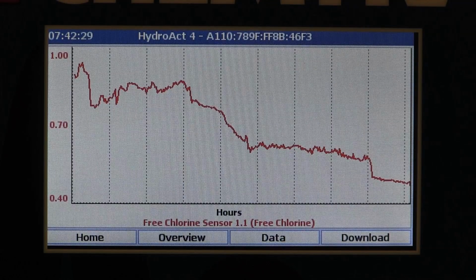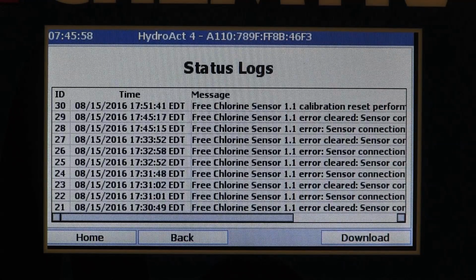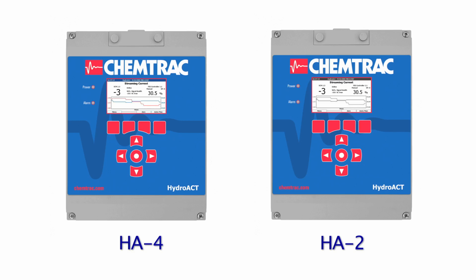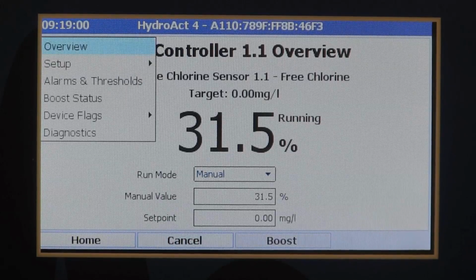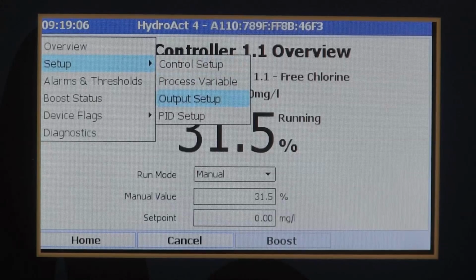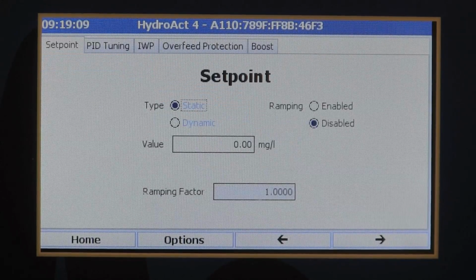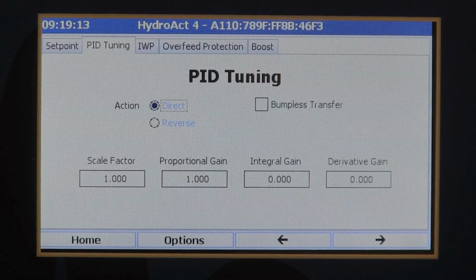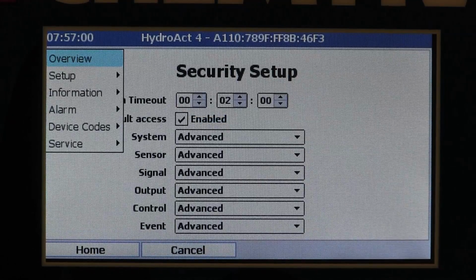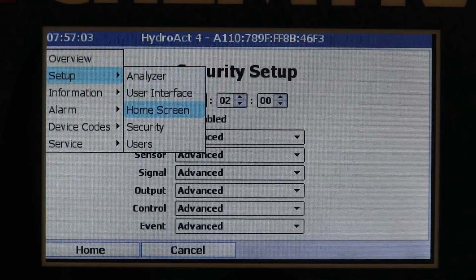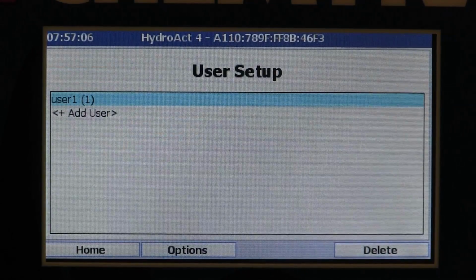The Hydroact Analyzer provides a graph display for reviewing historical readings, and a service log, which allows the user to view when the calibrations were performed, as well as when any alarm events took place. The HA4 model has a color display and a downloadable data log, while the HA2 model has a grayscale display and no data download capability. The Hydroact Analyzer can also be set up with single or compound loop PID control for applications that require automatic adjustment of chlorine addition. And when security features are required, the Hydroact can be set up with custom logins for multiple users with varying levels of access.